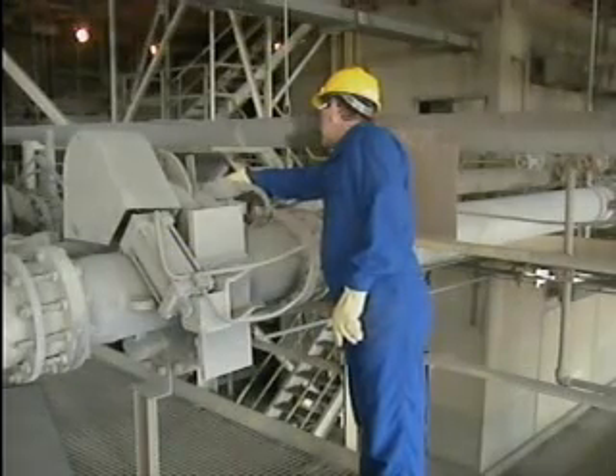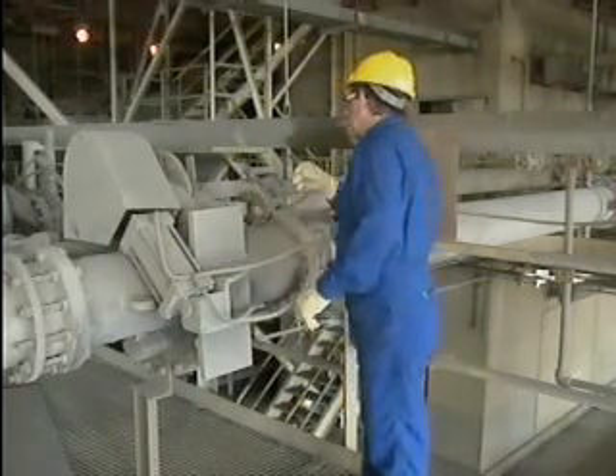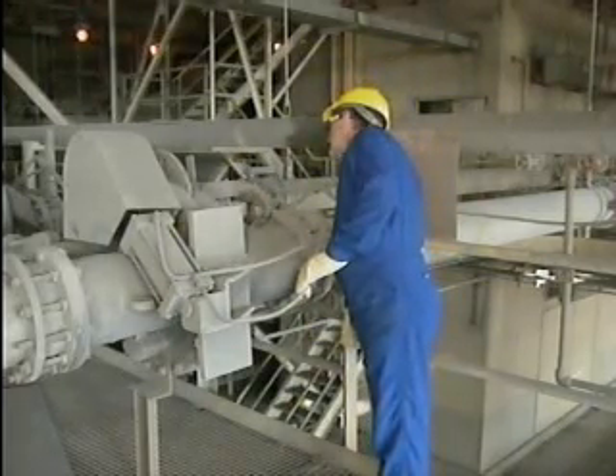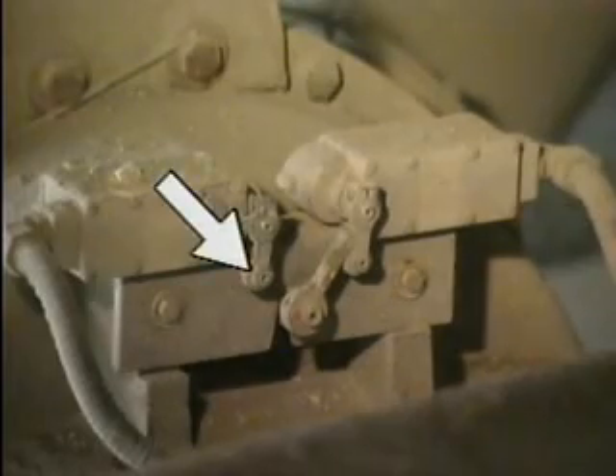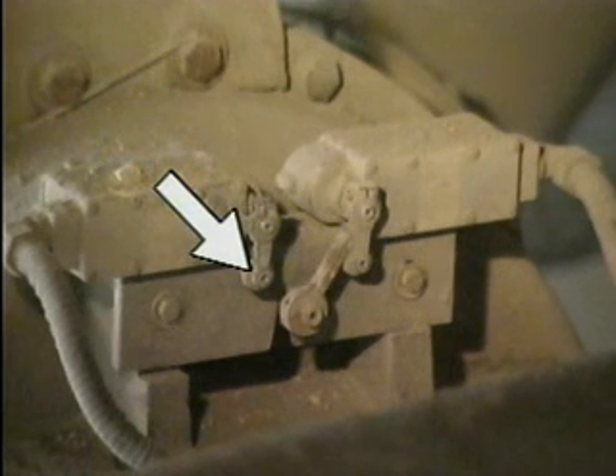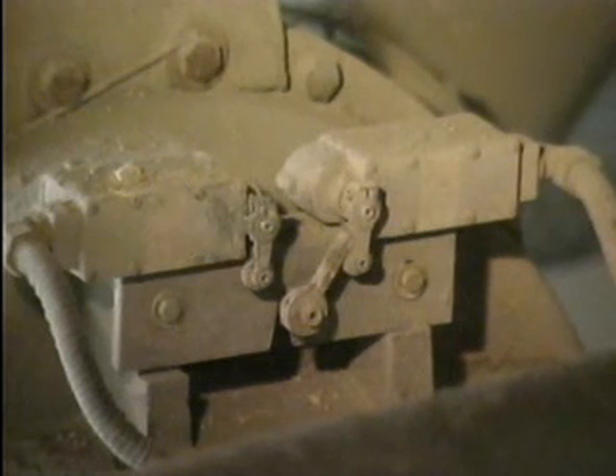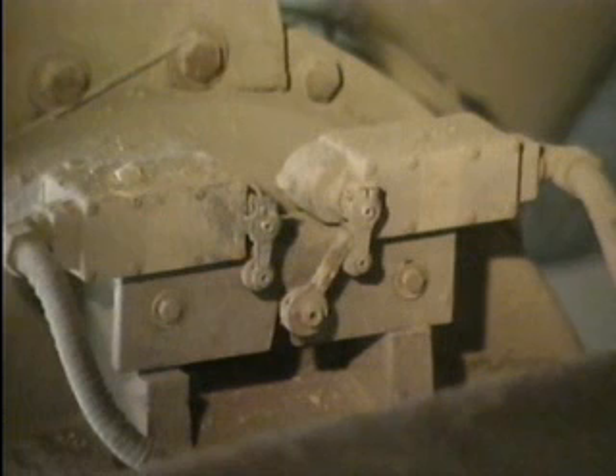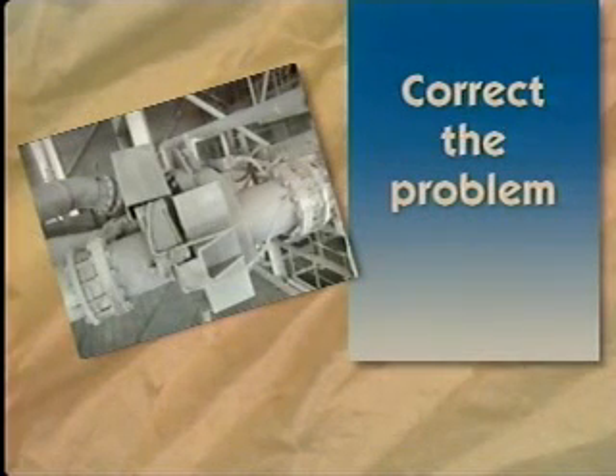The electrician goes to the silo crossover valve that's associated with the suspect limit switch. During his inspection, he finds that one of the limit switch control arms has become loose. Since the actuator cannot make contact with the control arm, the limit switch cannot change states from open to closed. Now that the electrician has determined that the crossover valve has malfunctioned, he needs to correct the problem.